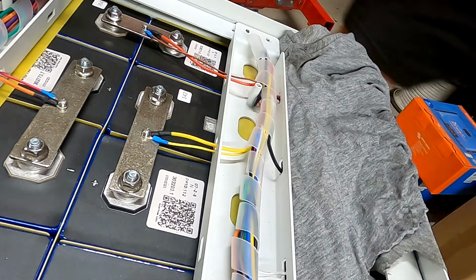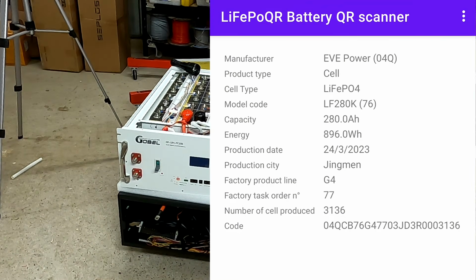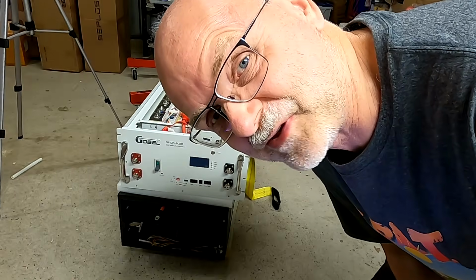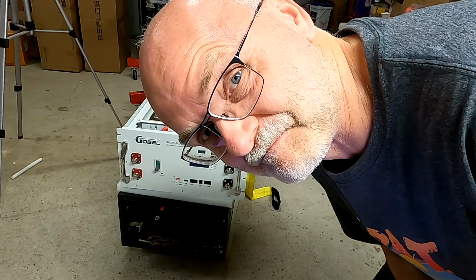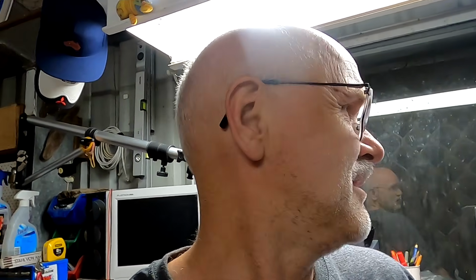Oh yes, got it. We have the EVE Power 04Q lithium iron phosphate LF280K, 280 ampere hours. Production date is the 24th of March 23, so that means they cannot be tested on the 7th of January, right? So I wonder if these are 280 ampere hour cells, why are they tested with 302, 303 ampere hours? And they still have got a B stamped on the QR code, so obviously they haven't failed because of the capacity then.